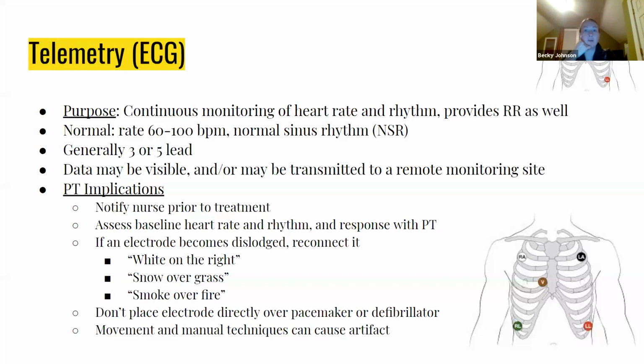We talked about a normal heart rate and its normal sinus rhythm. Typically in the hospital, when this is being monitored continuously, you're going to see either a 3-lead EKG or a 5-lead EKG. And sorry, I always use EKG and ECG interchangeably. I just can't decide which one I like better. So this is the layout you'll see when it's 3 or 5. Remember, to get a full-blown EKG in order to tell if somebody is, for instance, having a STEMI, one of you mentioned during class, you would need a full 12-lead EKG. So those are still done intermittently if somebody's having cardiac issues, but these are the type that you'll see for continuous monitoring to display on your screen.